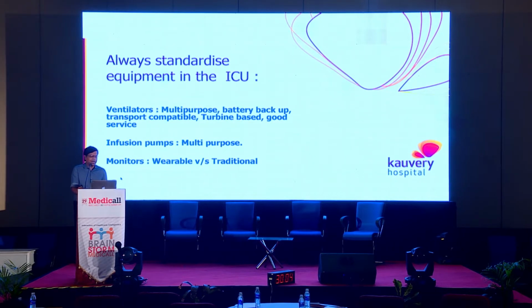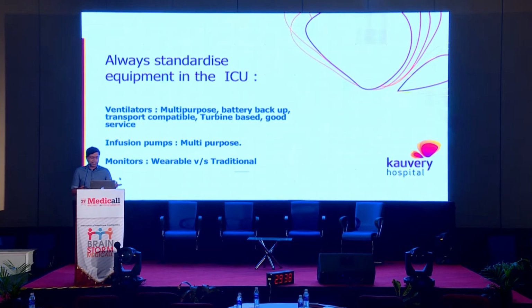We work in a hospital which has got everything, so we have compressed oxygen, we have compressed air. If you work in a hospital where you do not have compressed oxygen and air, then it's important to buy a ventilator that is turbine based. These ventilators don't run on compressed air. They use turbines, they themselves take air from the atmosphere, compress it and push it. So it's important to think about these things when you're buying, and it's also important to check that the ventilators offer good service backup later on.